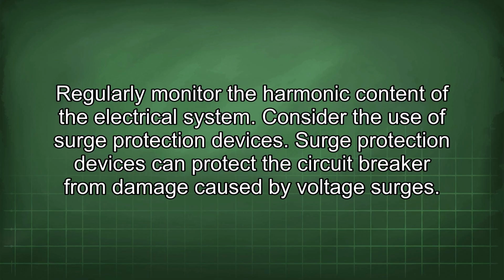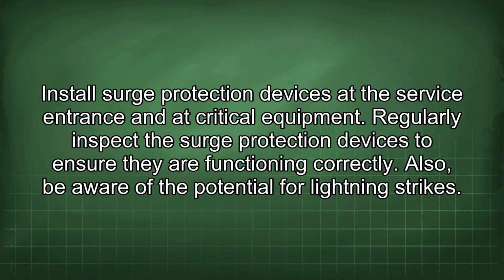Consider the use of surge protection devices. Surge protection devices can protect the circuit breaker from damage caused by voltage surges. Install surge protection devices at the service entrance and at critical equipment. Regularly inspect the surge protection devices to ensure they are functioning correctly.